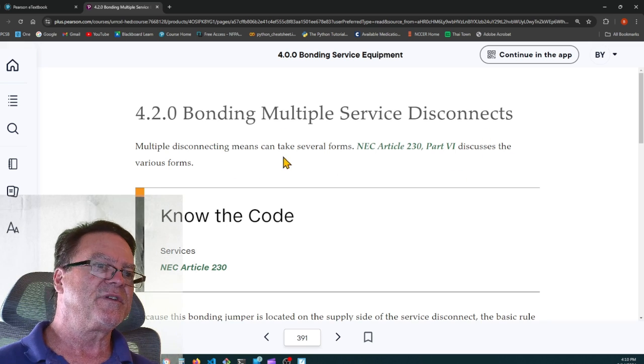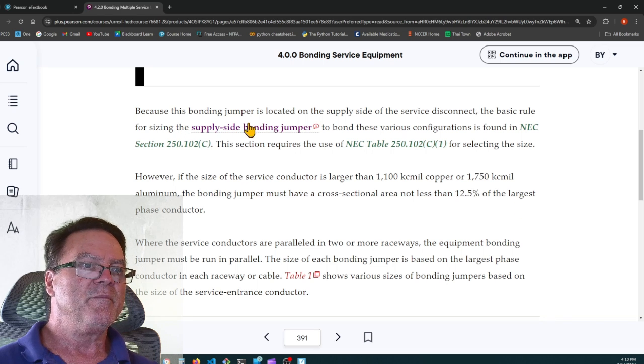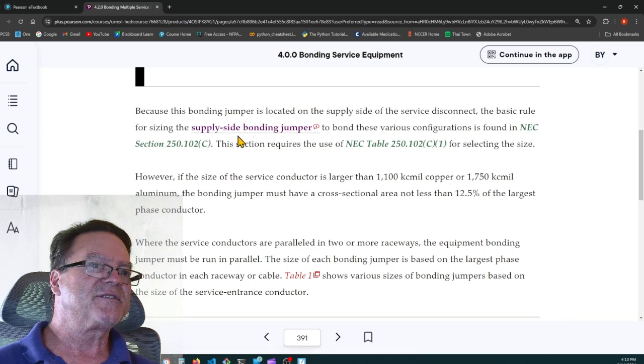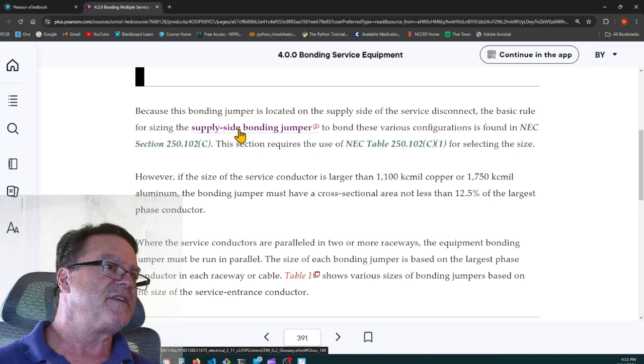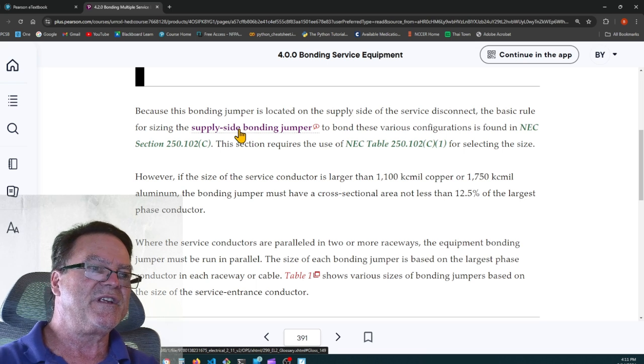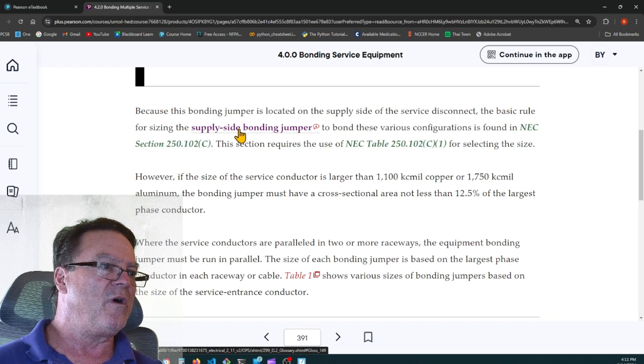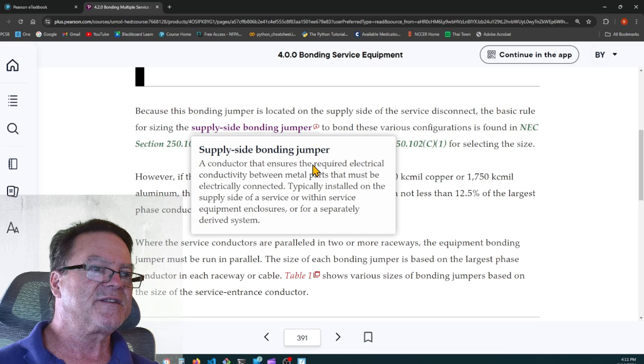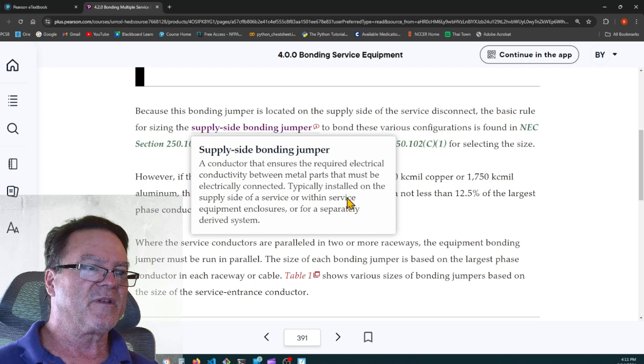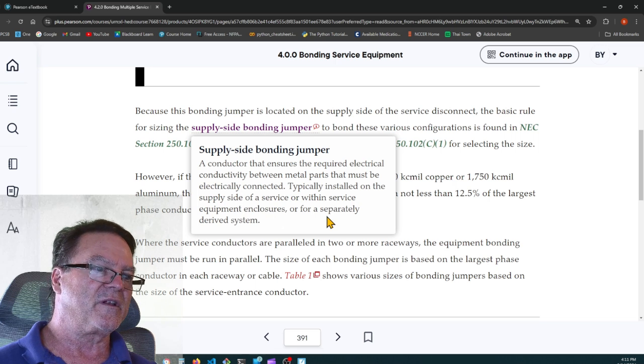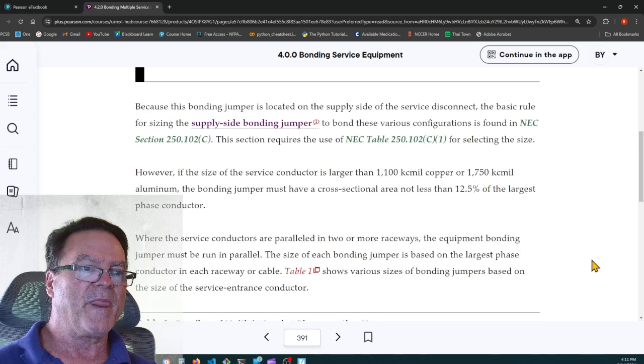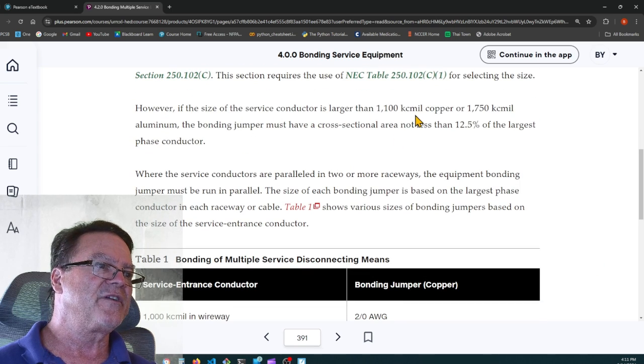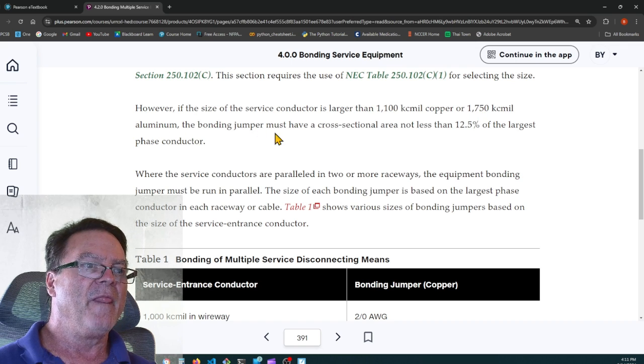Bonding multiple services. Multiple disconnecting means can take several forms. NEC Article 230 Part 6 discusses the various forms. Because this bonding jumper is located on the supply side of the service disconnect, the basic rule for sizing the supply side bonding jumper to bond these various configurations is found in NEC section 250.102C. This section requires the use of table 250.102C1 for selecting the size. The supply side bonding jumper is a conductor that ensures the required electrical conductivity between metal parts that must be electrically connected. Typically installed on the supply side of the service or within the service equipment enclosures or for separately derived systems. All right. It says, however, if the size of the service conductor is larger than 1,100 kcmil copper or 1,750 kcmil aluminum, the bonding jumper must have a cross-sectional area of not less than 12.5% of the largest phase conductor.